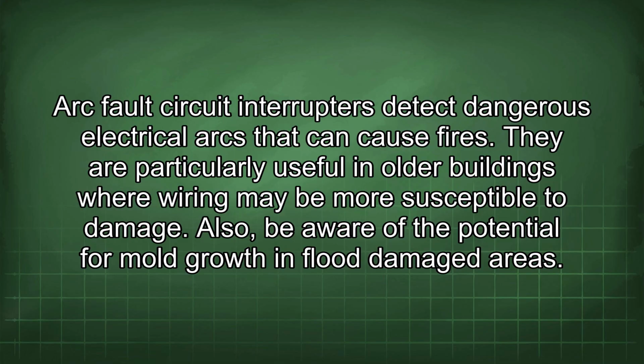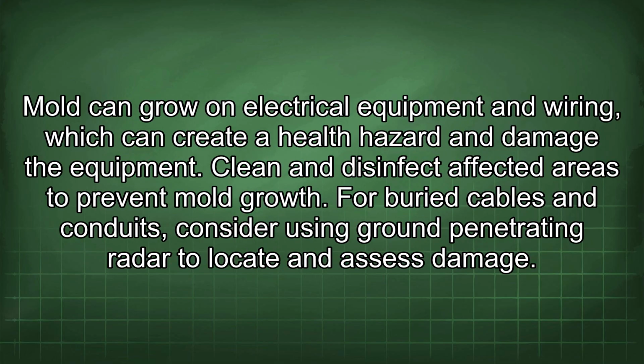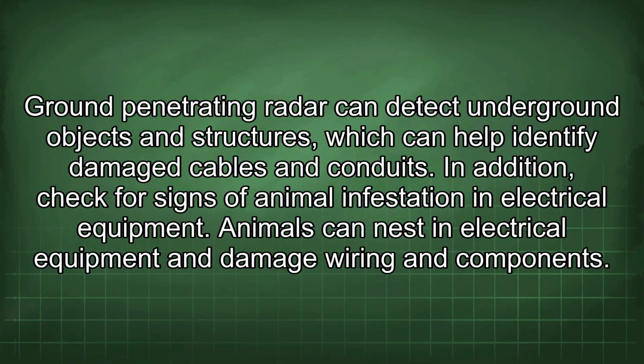Also, be aware of the potential for mold growth in flood-damaged areas. Mold can grow on electrical equipment and wiring, which can create a health hazard and damage the equipment. Clean and disinfect affected areas to prevent mold growth. For buried cables and conduits, consider using ground-penetrating radar to locate and assess damage. Ground-penetrating radar can detect underground objects and structures, which can help identify damaged cables and conduits.